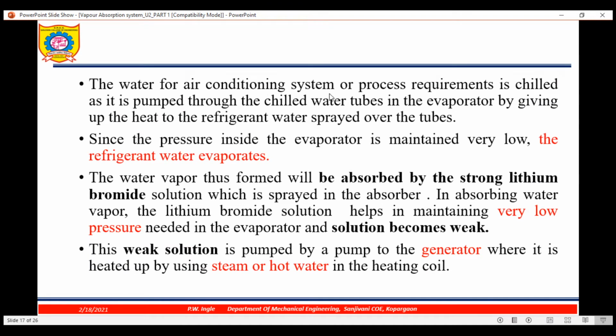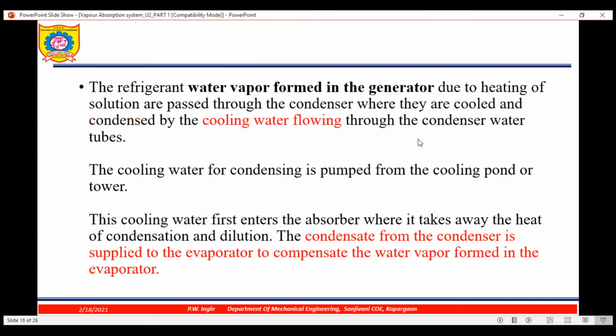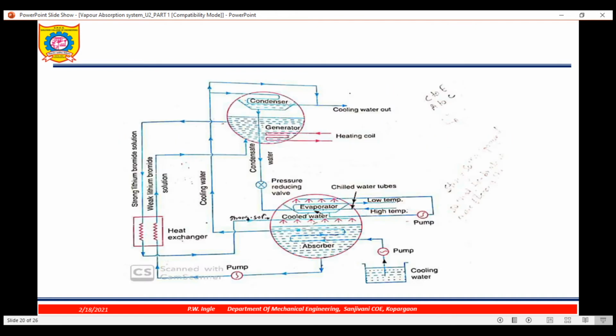Now the water for the air conditioning system or process requirement is chilled as it is pumped through the chilled water tube in the evaporator, by giving up its heat to the refrigerant water sprayed over the tube. So how is it working? First thing is water. Now, what is the main purpose? The main purpose is to get chilled water.